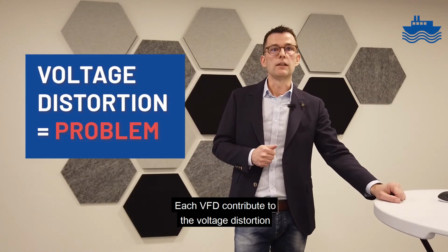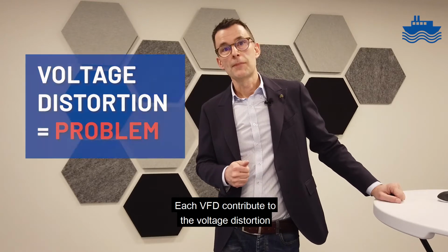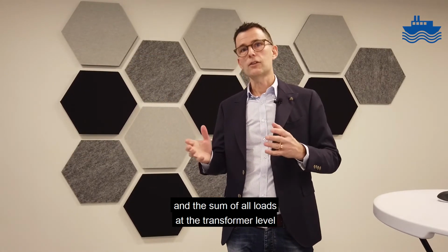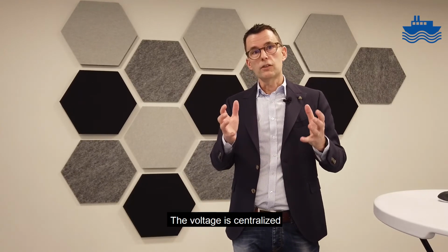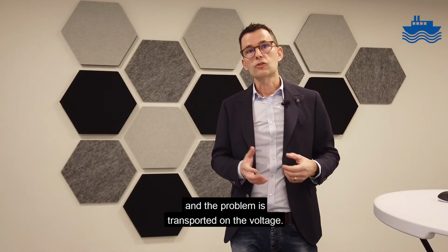Each VFD contributes to the voltage distortion, and the sum of all loads at the transformer level creates the problem. The voltage is centralized, and the problem is transported on the voltage.